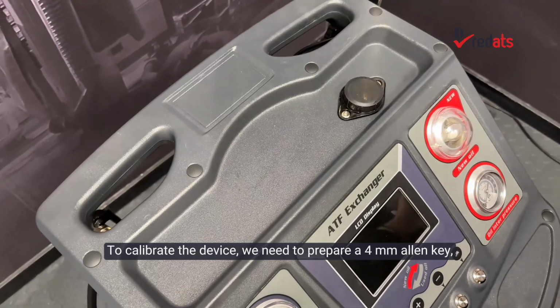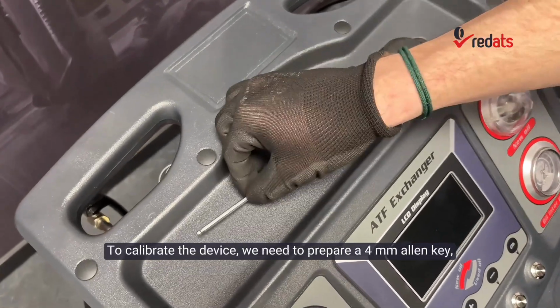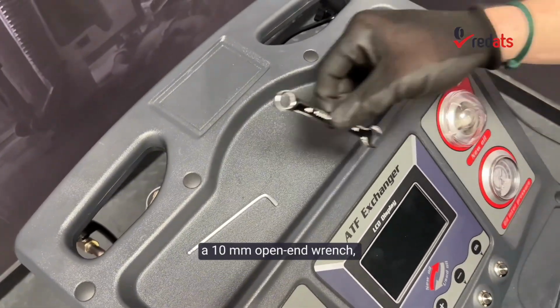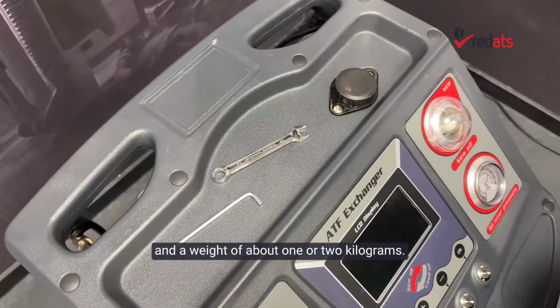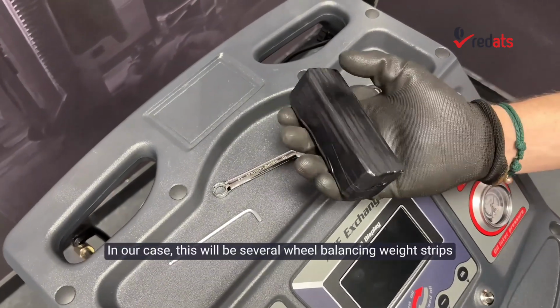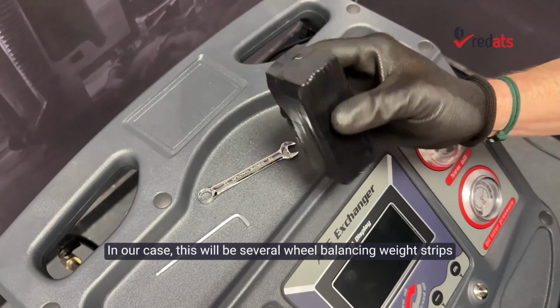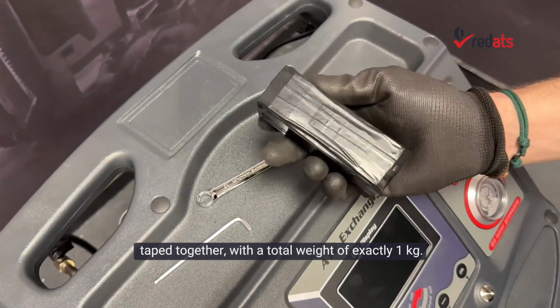To calibrate the device, we need to prepare a 4mm Allen key, a 10mm open-end wrench, and a weight of about 1 or 2 kilograms. In our case, this will be several wheel balancing weight strips taped together with a total weight of exactly 1 kilogram.